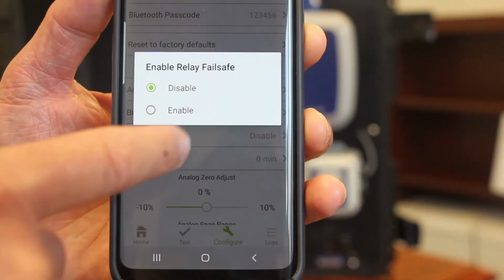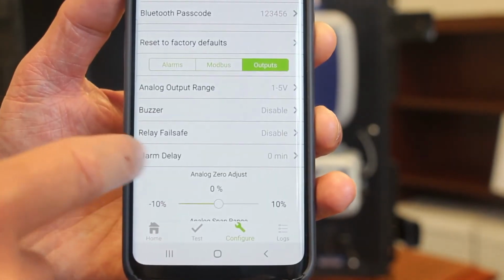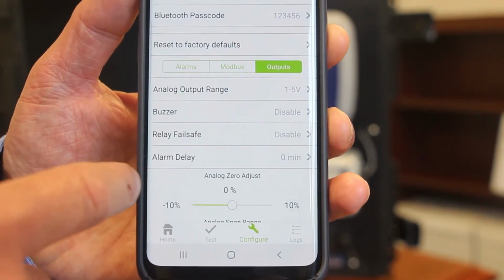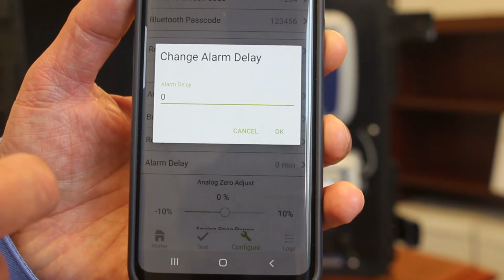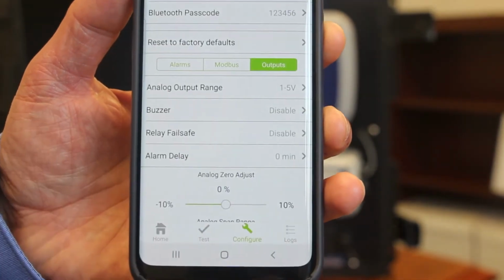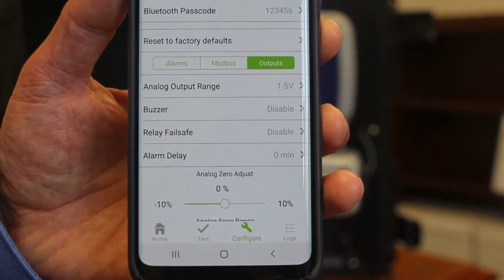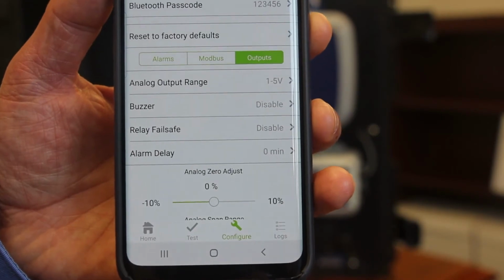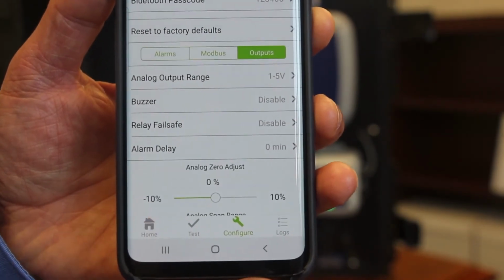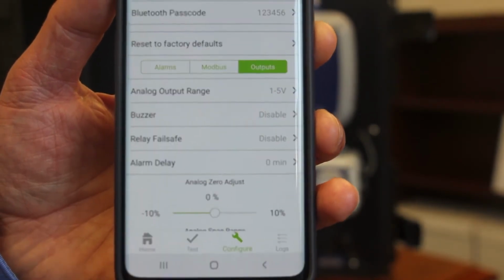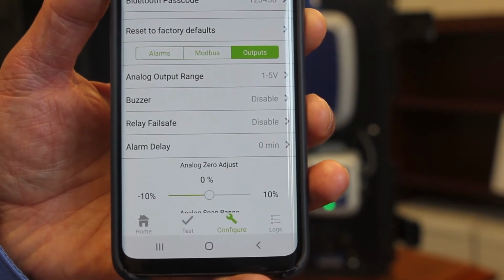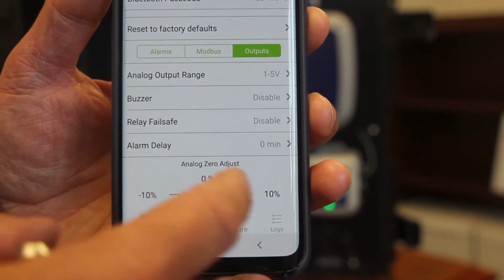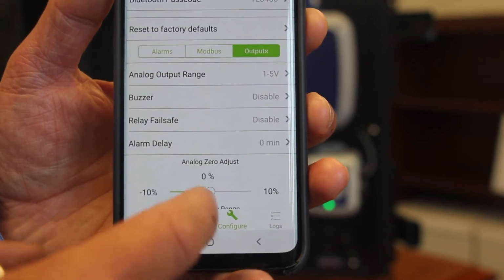And also, you have the capability to input an alarm delay. So for example, if you wish to have a small delay just to mitigate any potential risks of a false alarm, you can put maybe a 5 or 10 minute delay on the alarm. In addition, you can set your analog zero adjustment just using this simple slide bar here.